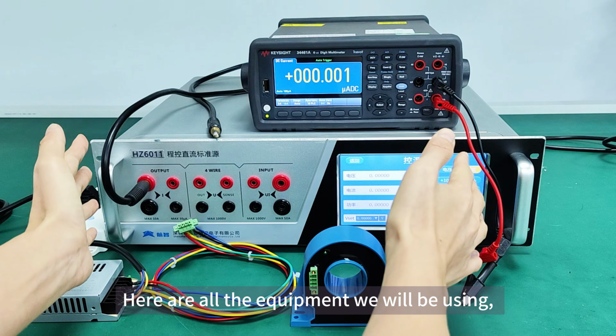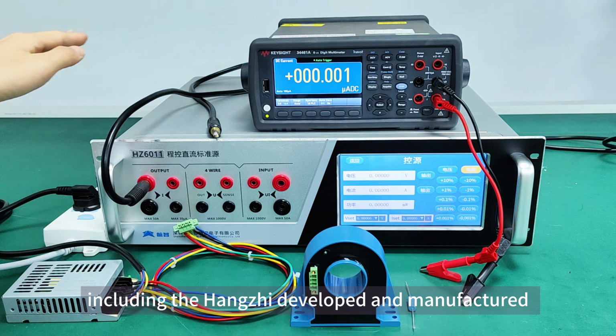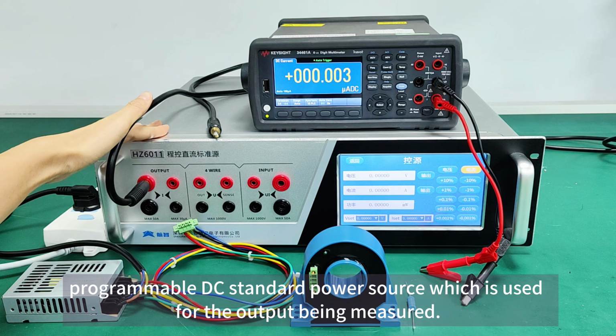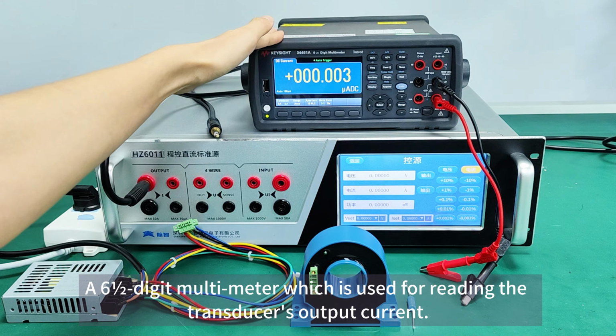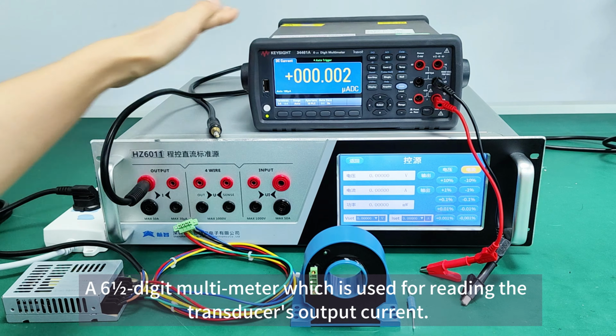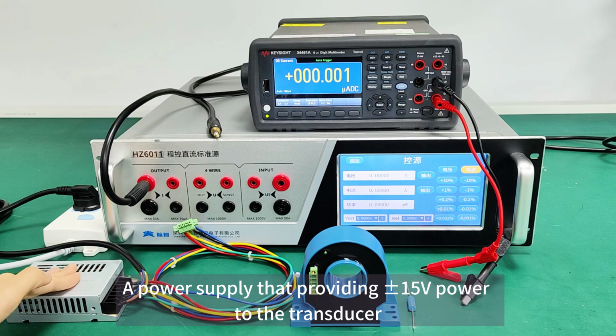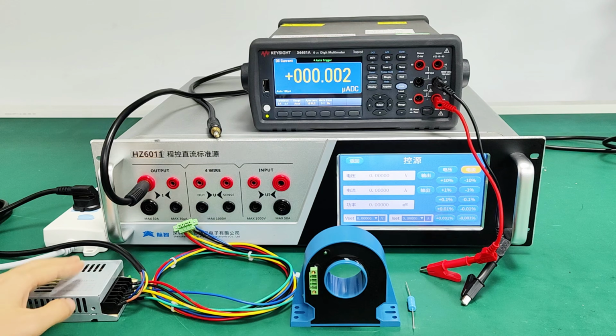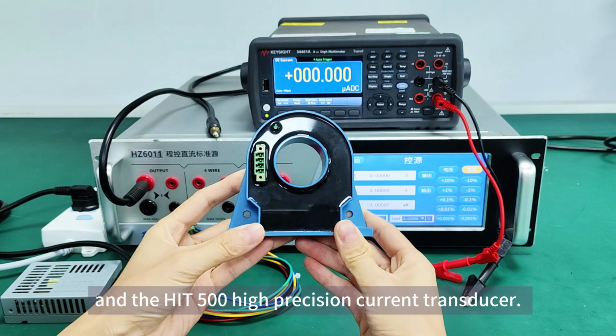Here is all the equipment we will be using, including the Hangzhi developed and manufactured programmable DC standard power source, which is used for the output being measured, a 6-digit multimeter, which is used for reading the transducer's output current, a power supply that provides 15V power to the transducer, and the HIT 500 high-precision current transducer.